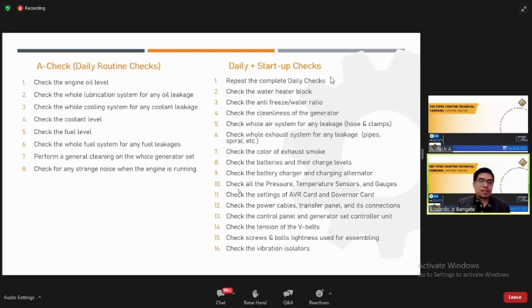We check the engine oil level. I'm not sure if everyone is doing this one because normally, with a good generator, we don't notice until a problem occurs. So we have to check the engine oil level, check the whole lubrication system for any oil leakage, check the whole cooling system for any coolant leakage, check the coolant level, check the fuel level, check the whole fuel system for any fuel leakages, perform general cleaning. As the engineer said earlier, Engineer Villarosa, always keep it clean when it comes to maintenance, keep it cool, keep it dry and keep it tight. The same goes for our generators.